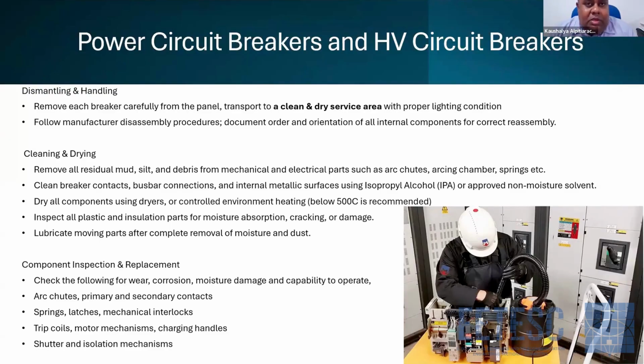arc flash. So any moving parts, springs, all moving parts shall be cleaned and lubricated, and check for wear, corrosion and all. Any part that cannot be recovered shall be replaced. So make sure when you are rehabilitating this particular device, any part which is worn is to be replaced, because you are doing a complete refurbishment for the particular device. Springs, latches, mechanical interlocks, or everything.